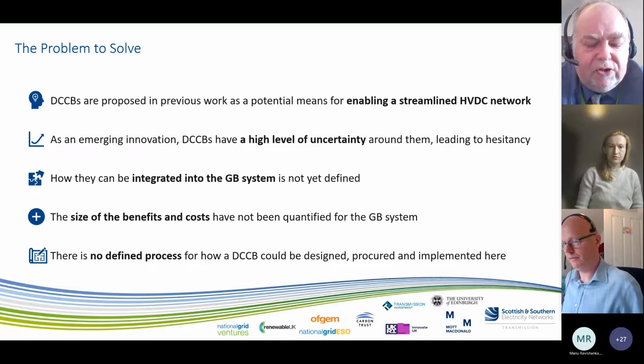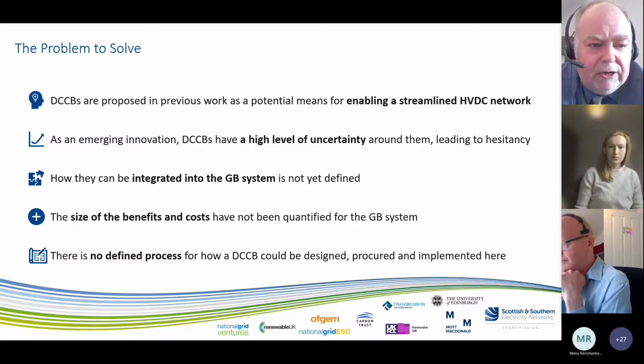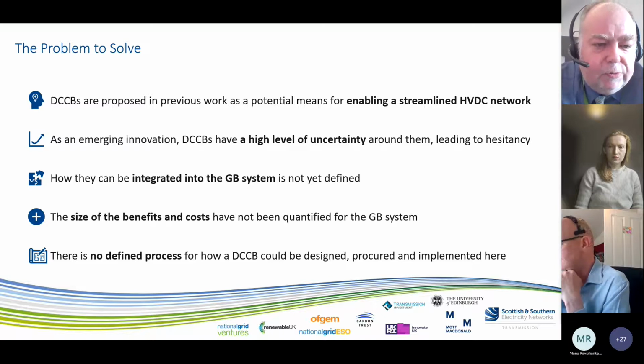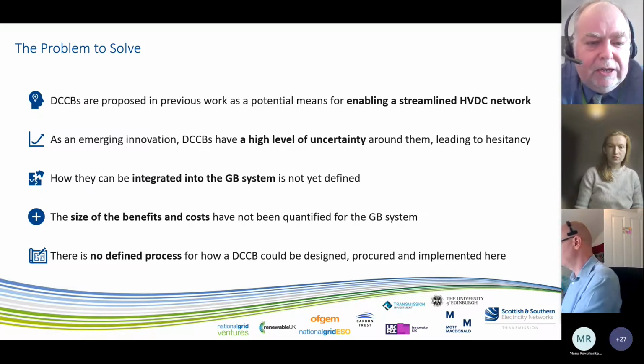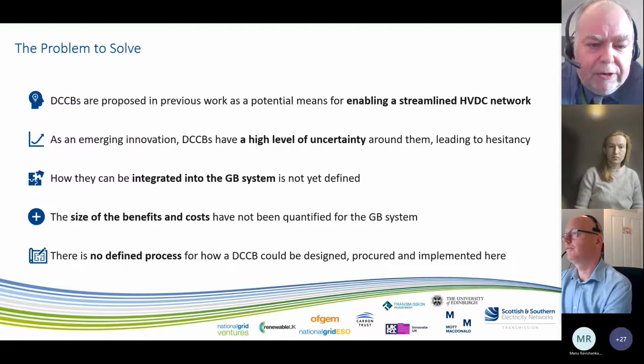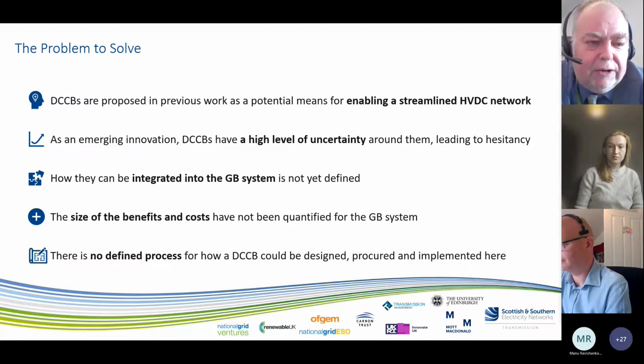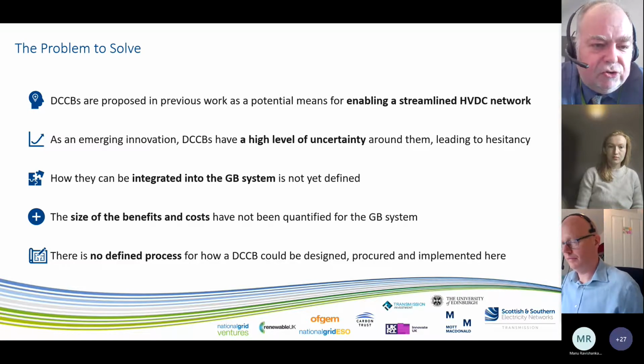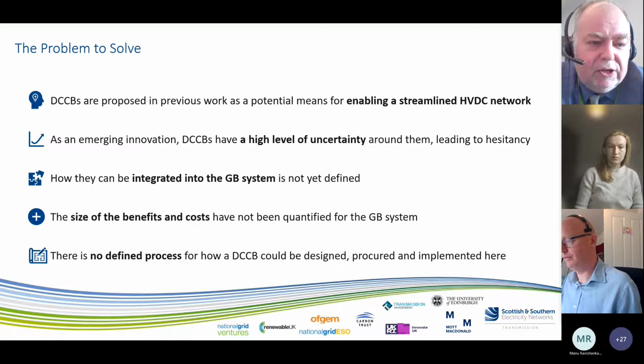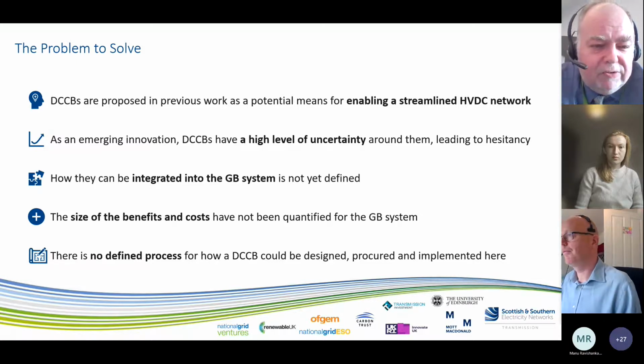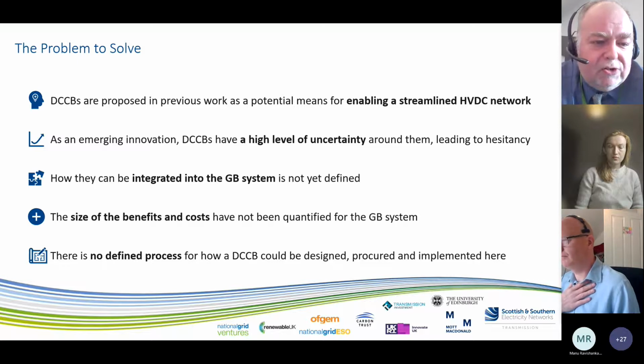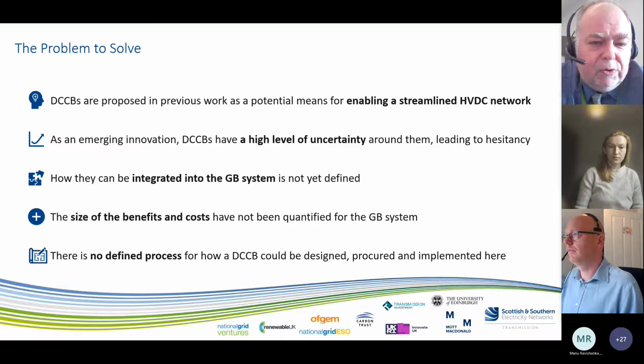The principal benefit we found for the use of DC hub technology, unlike the Chinese case where it's been maximization of reliability primarily that's driven DC circuit breakers. They're used predominantly on DC overhead lines in China, which are of course susceptible to lightning strikes. Within the GB system, with our system having a limited scale, being an island network, it has particular vulnerabilities to maximum loss of power, and it's really in limiting those maximum losses of power that the DC circuit breaker has its true value. So as you scale the concentrations of offshore wind, or indeed in the future if there was a large scale of hydrogen, the ability to use DC circuit breakers to limit the scale of the loss is critical.